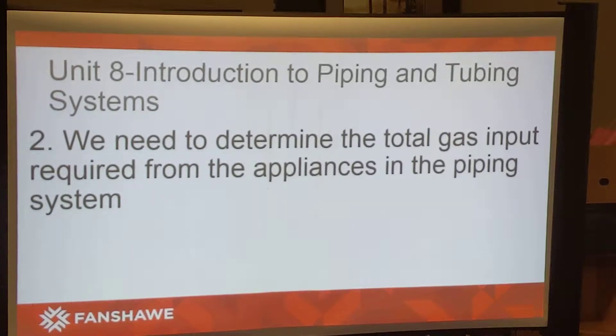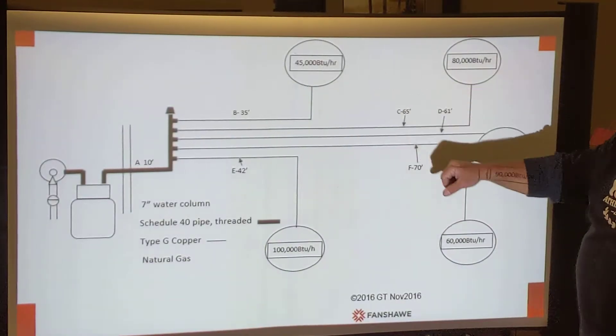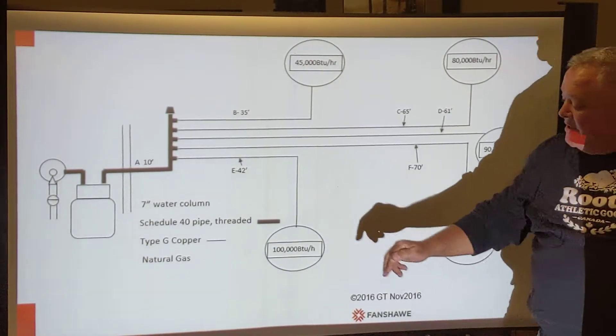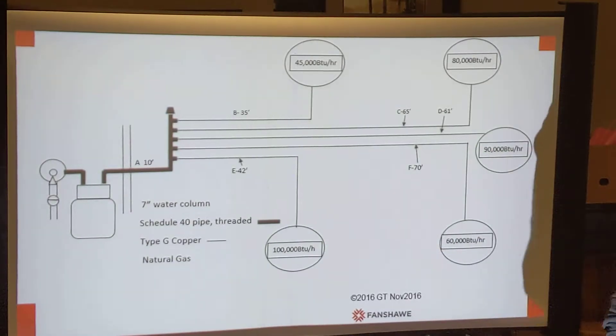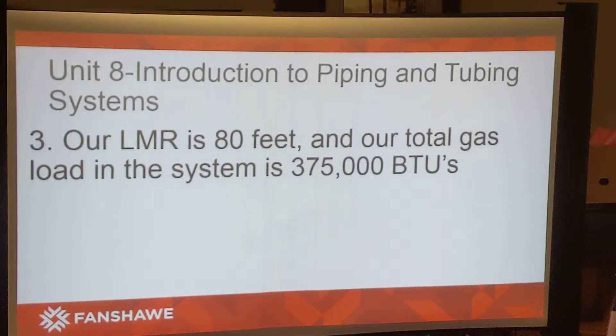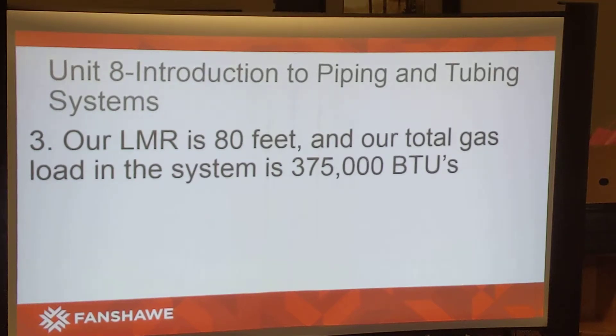Step number two: we need to determine the total gas input required from the appliances in the system. We're going to add up all of the BTUs — 45,000, 80,000, 90,000, 60,000, and 100,000 BTUs per hour. Our LMR is 80 feet and our total gas load in the system is going to be 375,000 BTUs per hour.